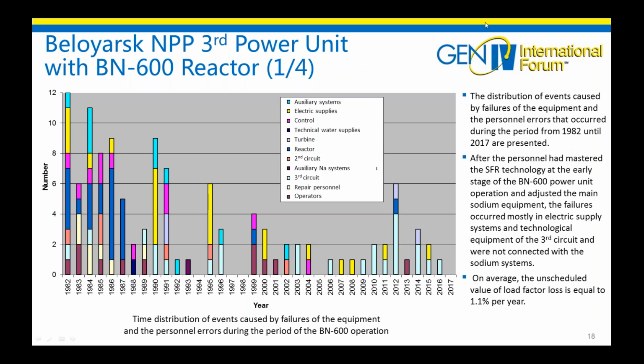This figure shows the time distribution of equipment failures and personnel errors that took place in BN-600 power units from 1982 till 2017. It should be mentioned that after the personnel mastered the sodium fast reactor technology at the early stages of the BN-600 power units' operation and adjusted the main sodium equipment, the failures occurred mostly in the electric supply system and technological equipment of the third circuit, and were not connected with the sodium system. The unscheduled failure of load factor loss is equal to 1.1% per year.